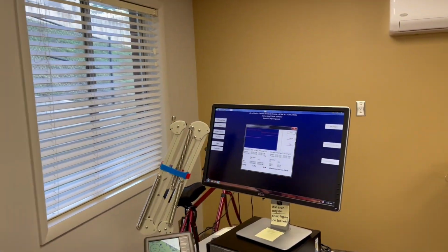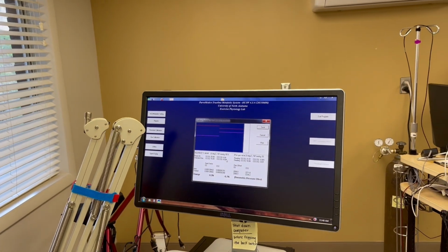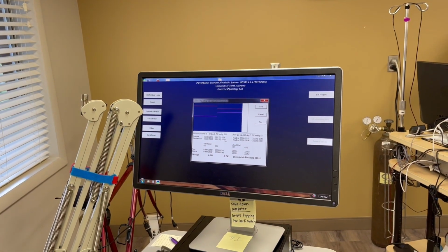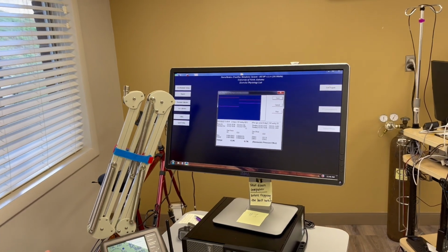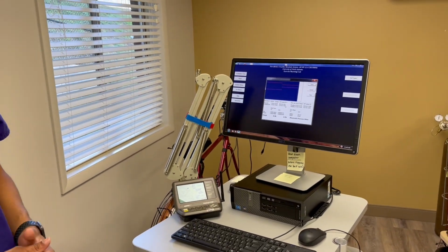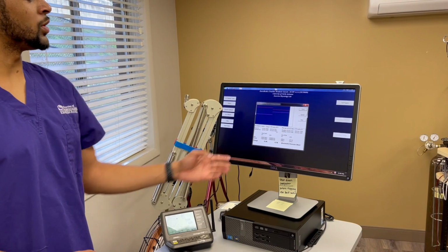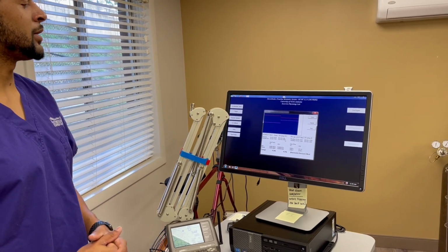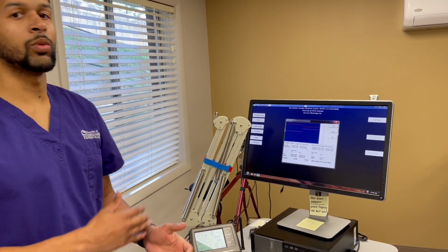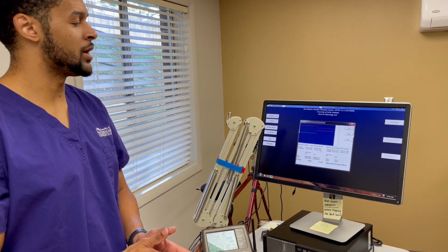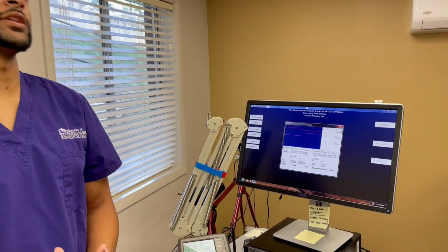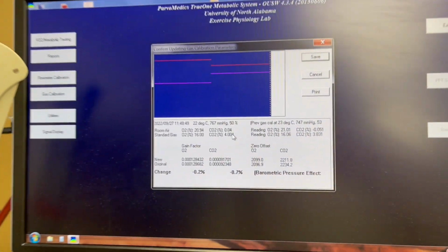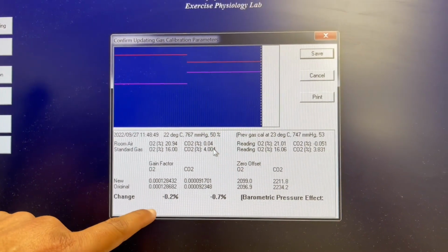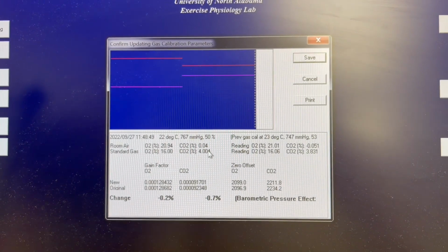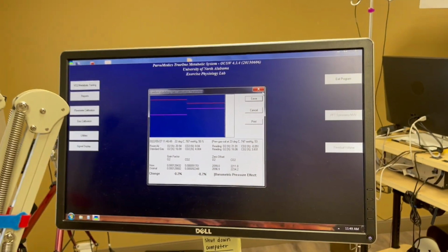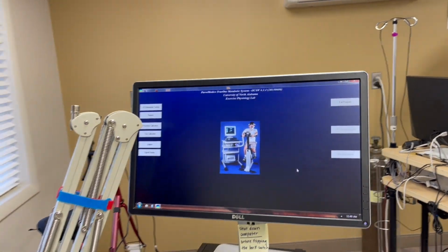Two things to note. One thing to note is before you even start the gas cal, make sure that you take off the sampling line on the back of the mixing chamber as we discussed earlier. And then also, once you do the gas cal, you want to make sure that the change is within less than 1%. So anything lower than 1%, you're okay. It can be a positive or a negative value. That doesn't matter. So on here, we have negative 0.2, meaning that we're good to go. And so we can save this calibration and then move on to the next one.